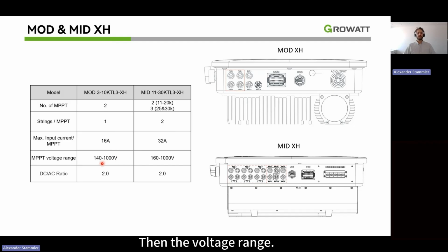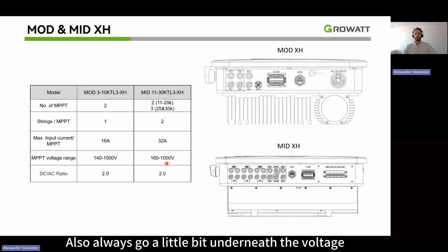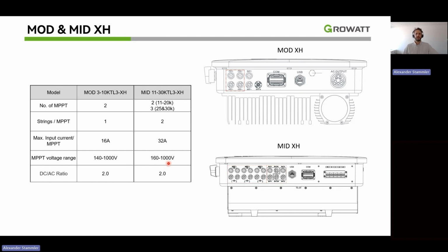Then the voltage range, so also starting voltage is 140 and here 160. I recommend not to go over this 1000 volts when you plan the system. Also, always go a little bit underneath the voltage because there's still some discrepancy, and I would not go up to the limit.